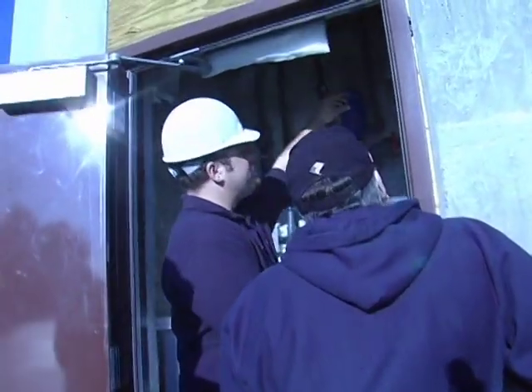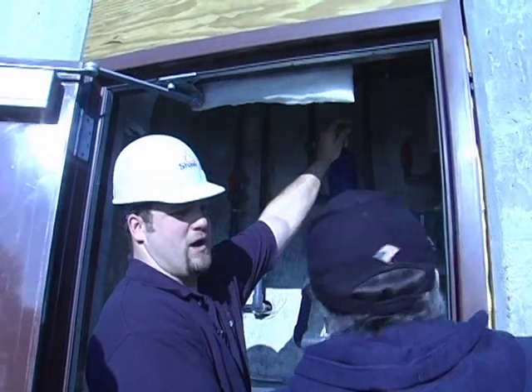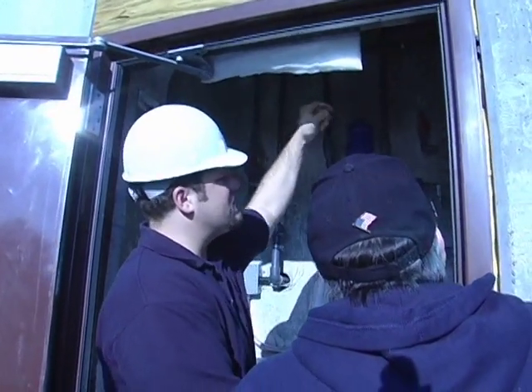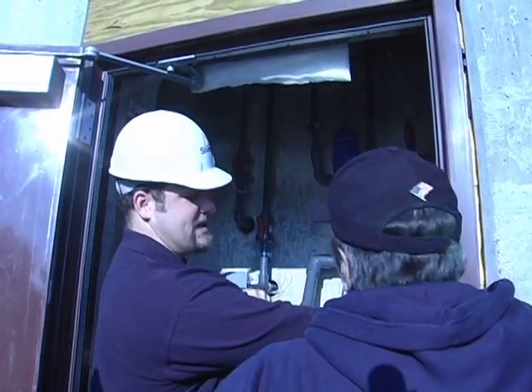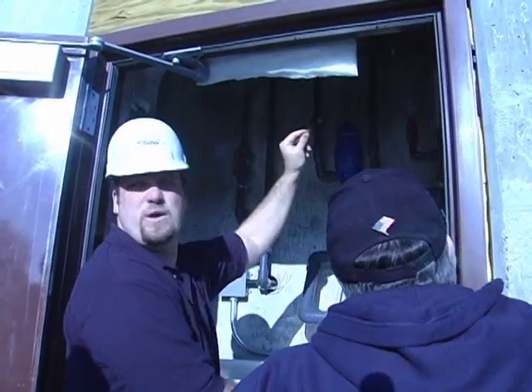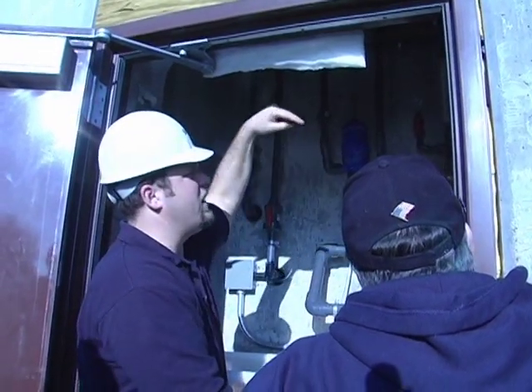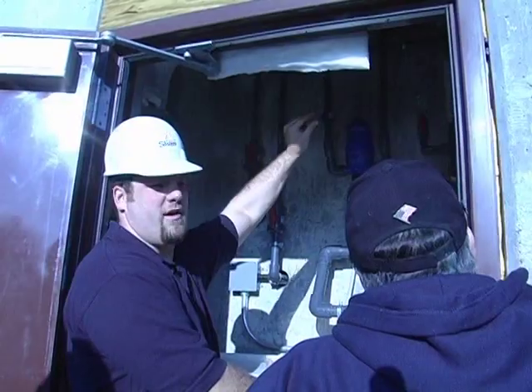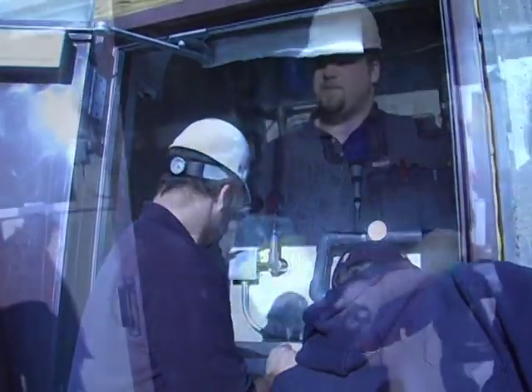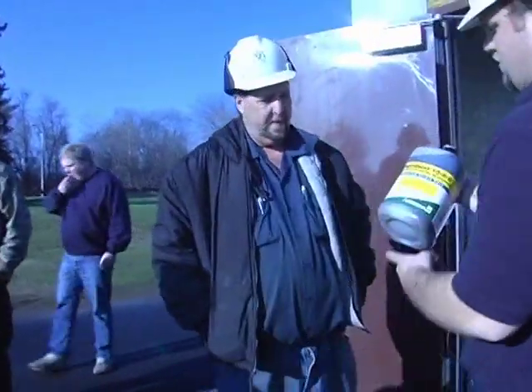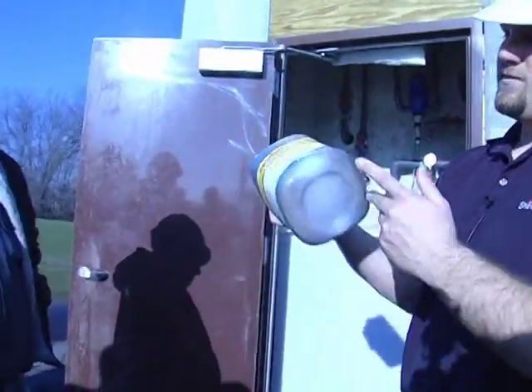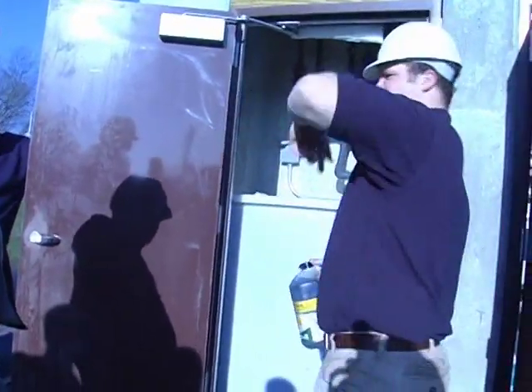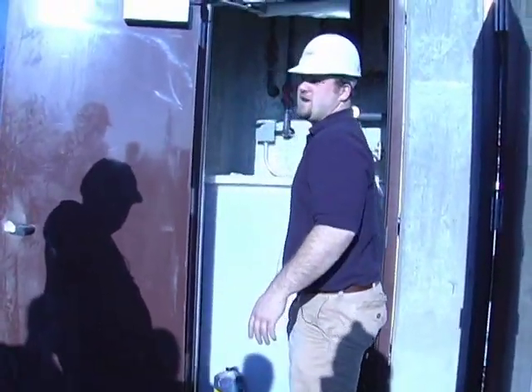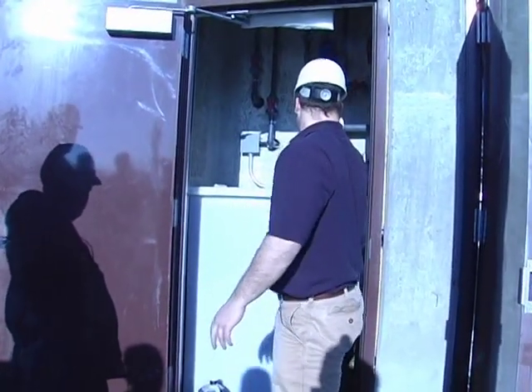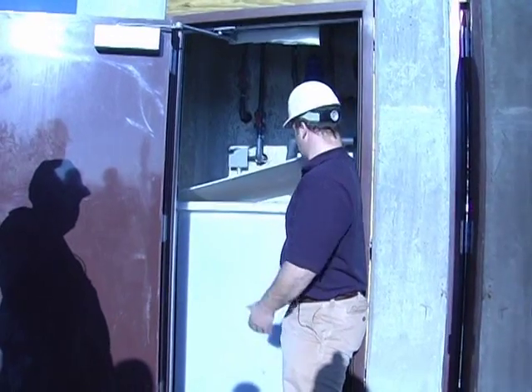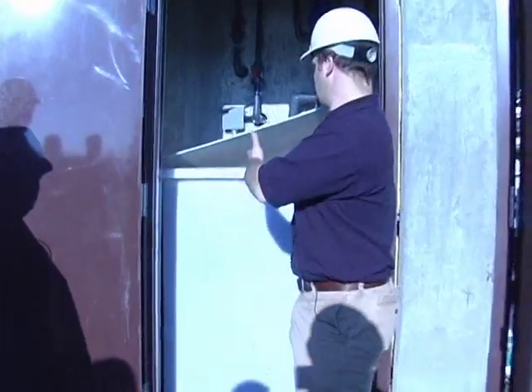You can see there's that magnet in there, and then it goes down to a smaller section. Right where it goes down to the smaller section, there's a fine ring on the top of that, and you can kind of see it over here on this one a little bit better. That's where you take the reading on that rotameter, from a little ring around the top quarter of that magnet. This is the liquid nutrient that's added to the tank. You probably just have to shake it up a little bit, and then you dump it right in. It's water soluble. It's a PKN nutrient, phosphorus, potassium, nitrogen. You can see it in here. I've already filled it up with nutrients.